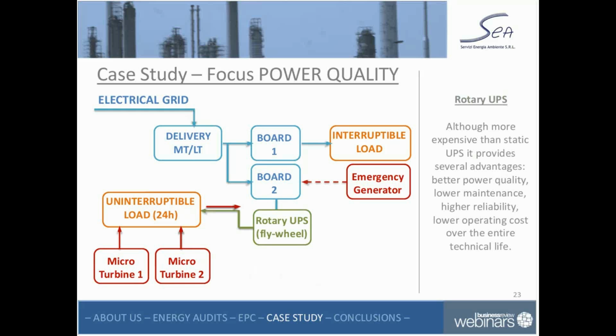We didn't use a stationary UPS based on batteries, but preferred the flywheel for a few reasons: better power quality, lower maintenance, high reliability, and lower operating costs, especially over the entire technical life, mainly because you don't have to change batteries once every 4 to 5 years. So this was our choice.